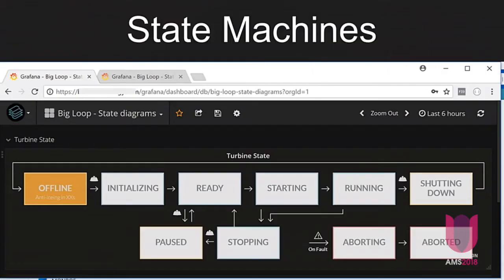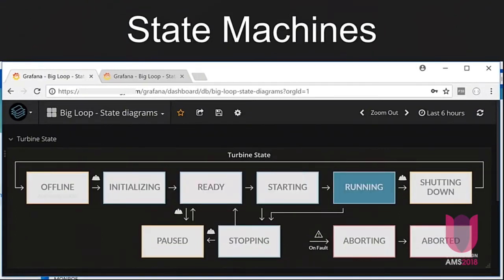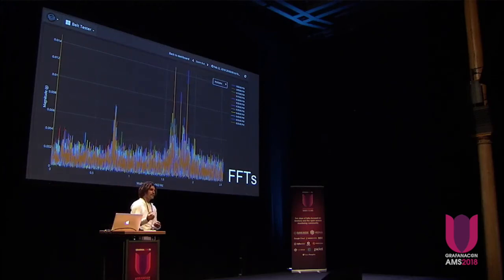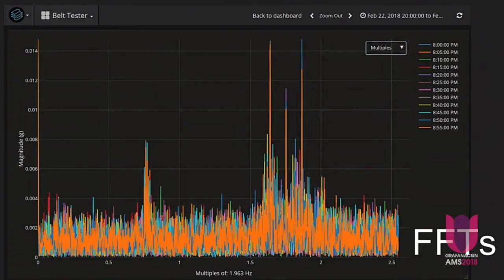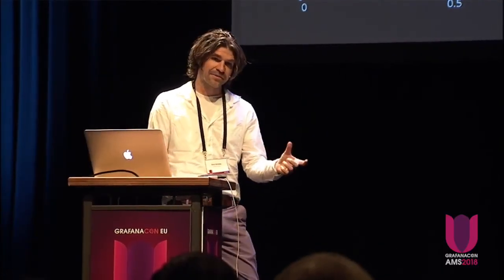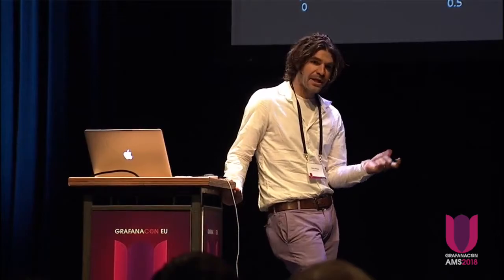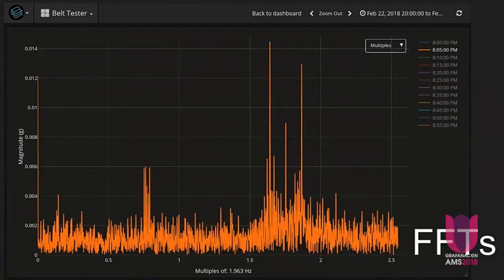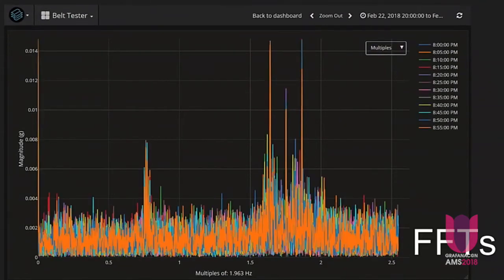The next one is obviously documenting the states, because people looking at this don't know what those states mean — like if I'm initializing, what does that mean, what does it go to? This is pretty simple: it walks through your states, so you're in running, you can tell as you're moving from state to state. These are all based on the same queries and the same data source. FFTs were another big one — understanding the health of the system is based a lot on vibration, so understanding behavior in the frequency domain. This is a modification of the Plotly panel showing over time where our key resonant frequencies are, and we can zoom into specific times across that query.